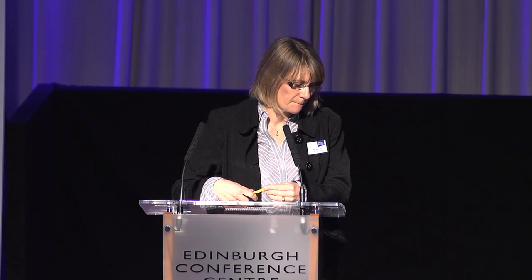So this device is essentially a non-invasive, non-destructive device, transmits a very small sinusoidal wave through the system and picks up either a +1 reflection or a -1, those corresponding to either a closed end or an open end. And if you actually measure the time the wave takes to go and come back again to the point of measurement, you can identify where the defective trap is, and that allows your team to go and fill the trap, and that would have averted, had it been used in Hong Kong, the cases where we would have known where the empty traps would have been.